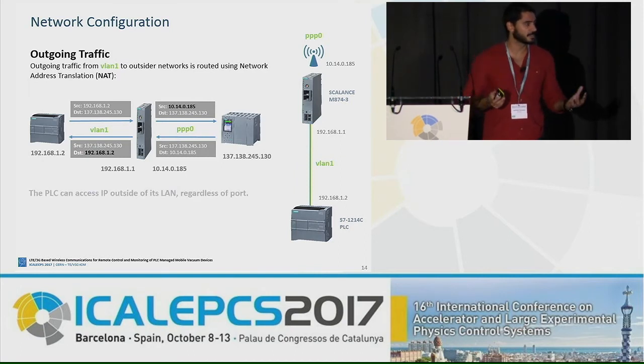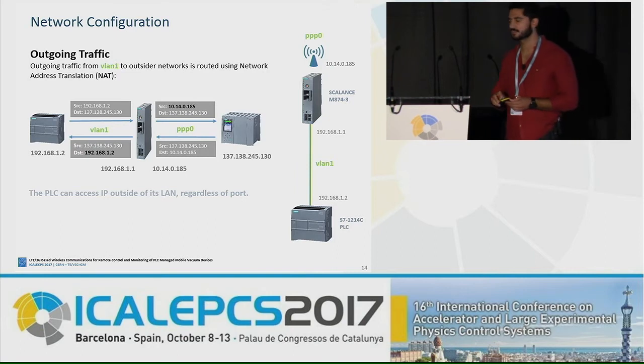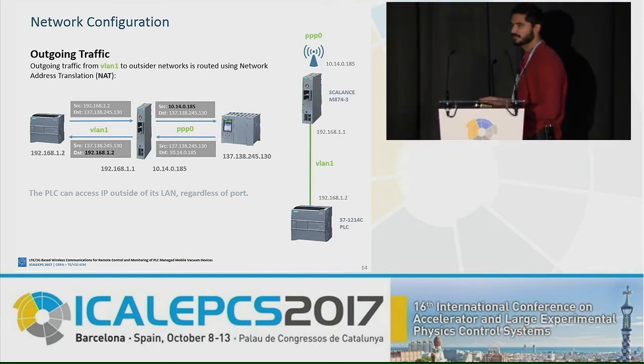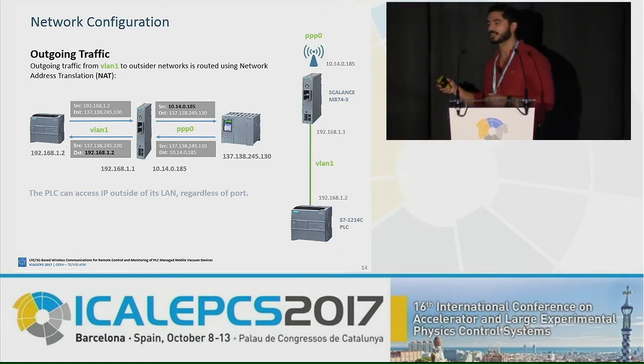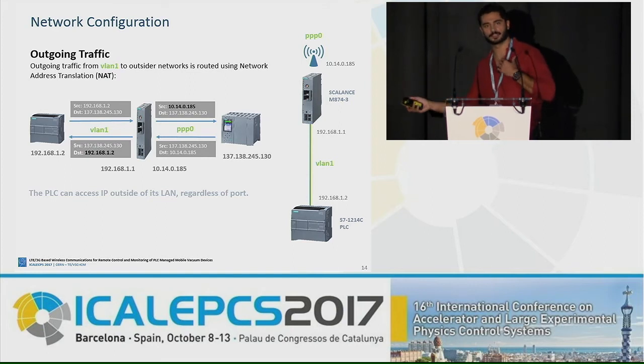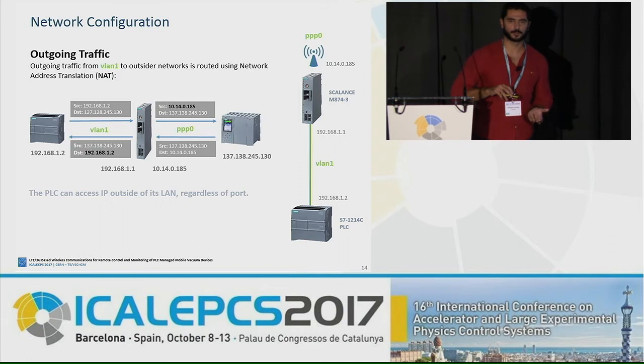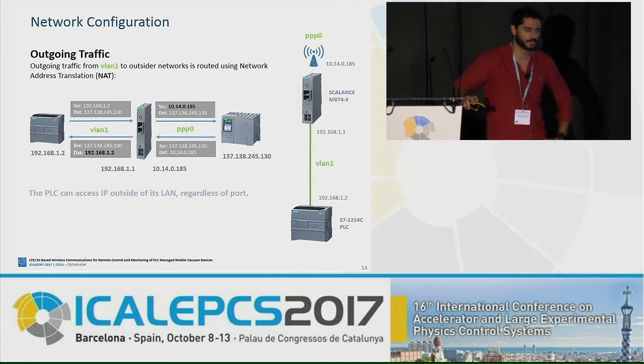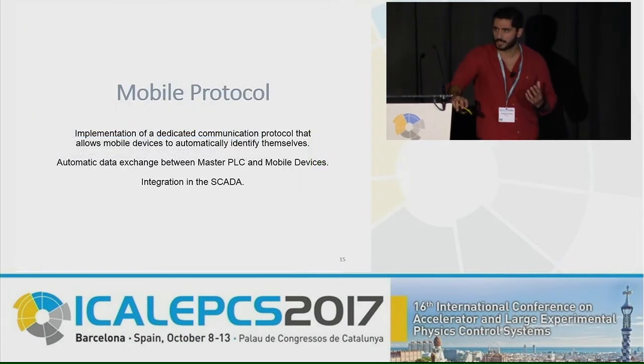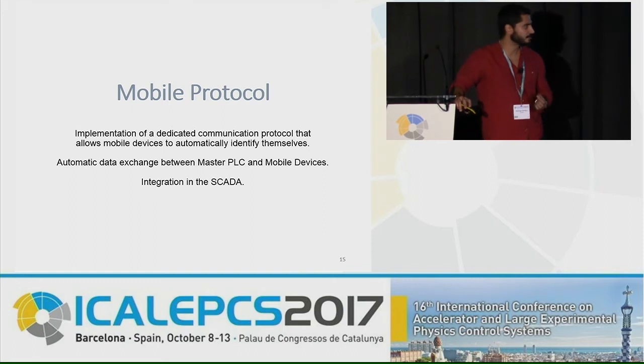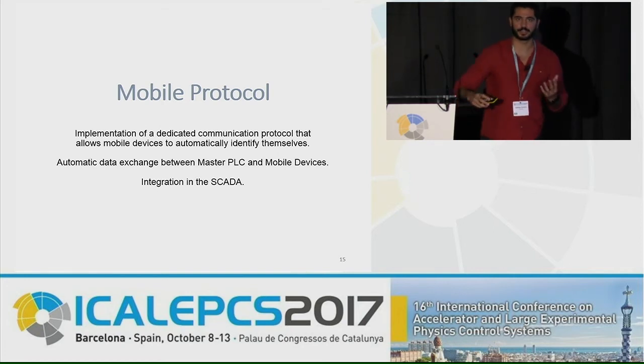With this network structure and configuration, we can access our slave PLCs through our SIM card, the same way regardless if it's a bakeout rack with a Step 7 300 or a mobile pumping group with a Step 7 1200. Now that we have this, we can start looking into the implementation of our mobile protocol, which is the part of our system that will integrate our devices into the SCADA.